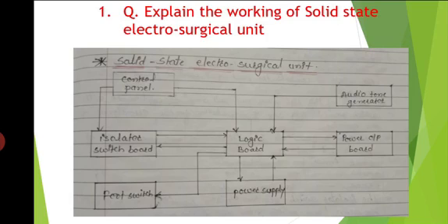An astable multivibrator generates 500 kilohertz square wave pulses. The output from this oscillator is divided into a number of frequencies by using binary counters. These are the frequencies used as system timing signals. The 250 kilohertz signal used for cutting is given to the power output, where it controls the push-pull parallel power transistor output stage.